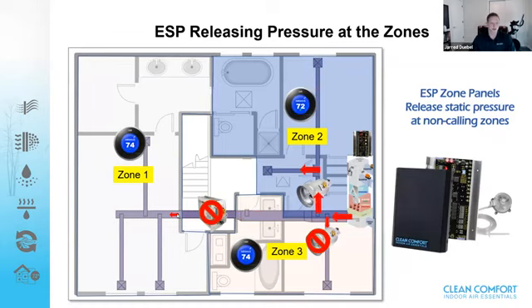As an example, this gives you an idea with ESP. Again, zone 2 is your zone calling. We're pushing all of our air to zone 2. However, with the zone 1 damper and zone 3 damper, we're going to just crack them ever so slightly to relieve some of that pressure.